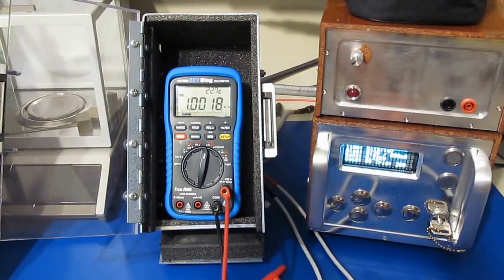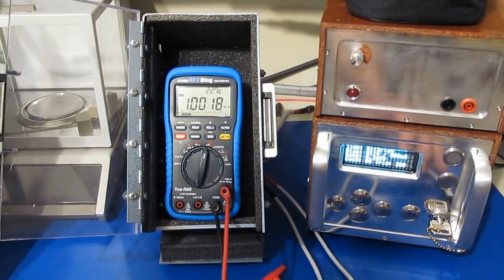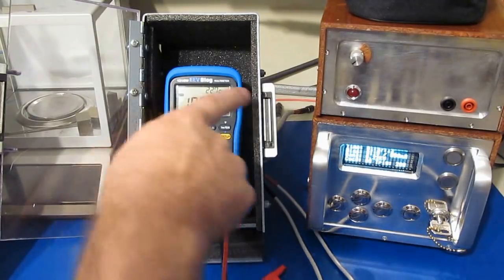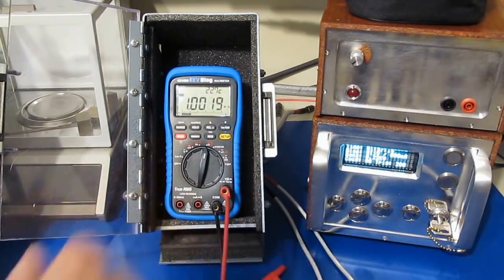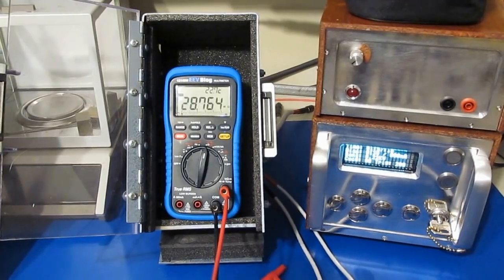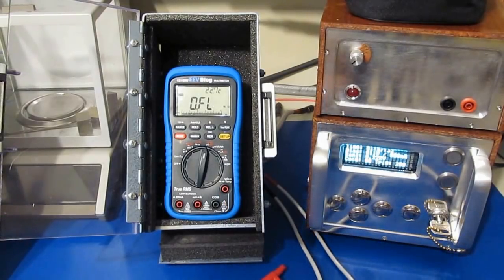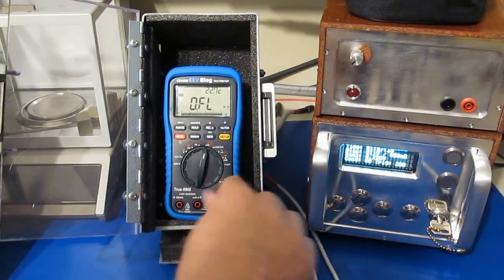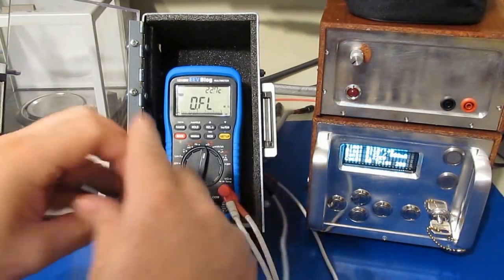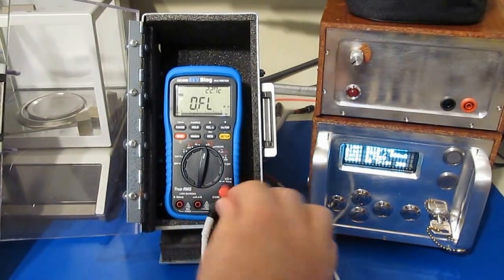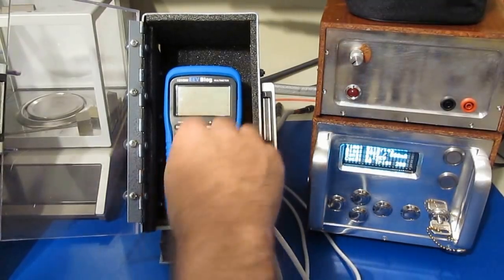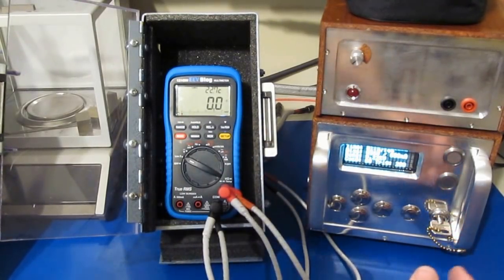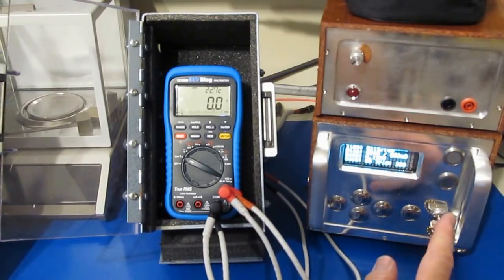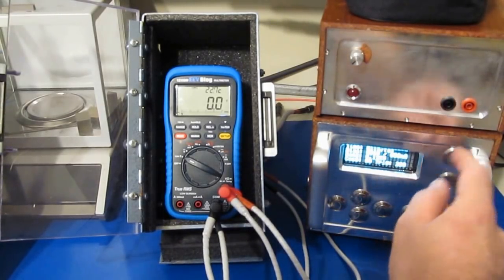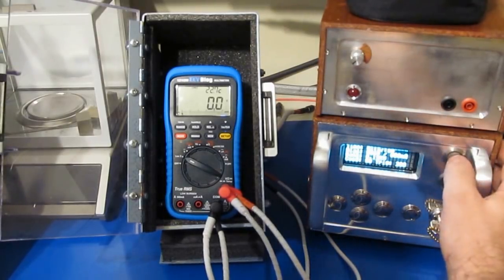Okay, so the meter passes functional just fine. Again, that was a 4000 volt peak with 100 microsecond full width half height. You can see the PTCs have had quite a bit of time to cool down. Everything is basically back to normal now. So I've reprogrammed our generator to put out the maximum voltage. Again, this is about 5.8 kV, and it's the most I can get out of this thing without changing over to the other generator. This is the top end. Again, we'll be applying 5 transients to each mode of the meter, positive and negative. We'll see if it survives this.